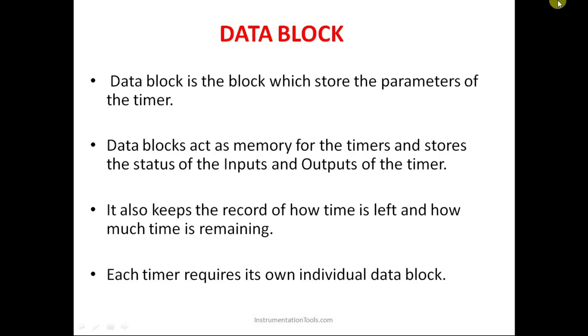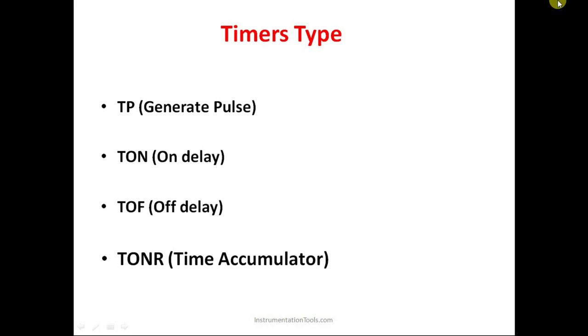Now let us see the different types of timers available in TIA Portal. The first one is TP — the generate pulse timer, used when you want an output to be high for a particular time. Next is TON — an on-delay timer, used to turn on the output after a delay. Then TOF — an off-delay timer, which provides a delay in turning off. Finally, TONR is a special case of the TON timer — a retentive on-delay timer.